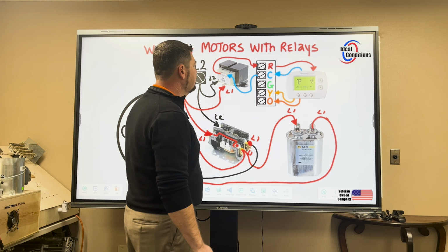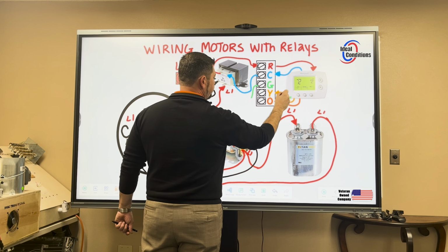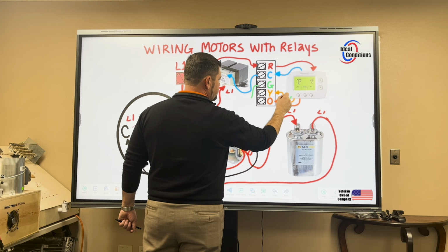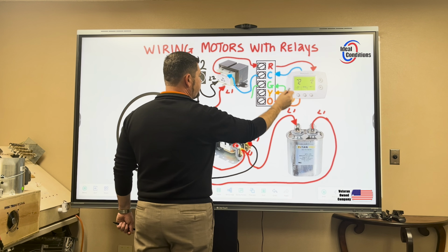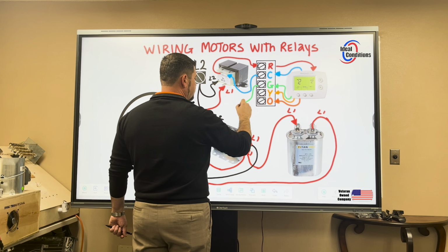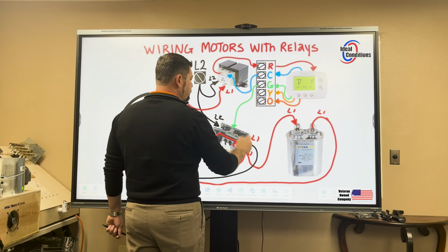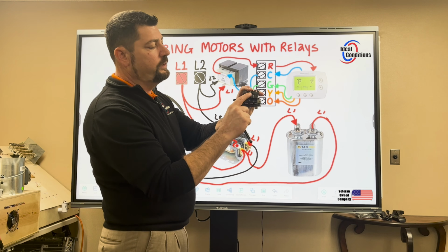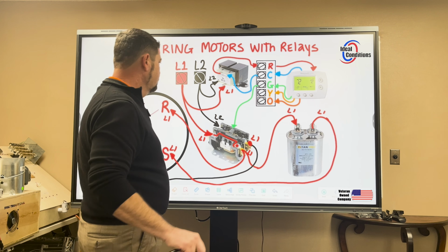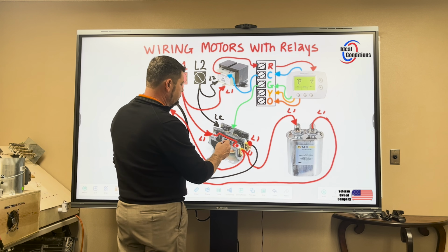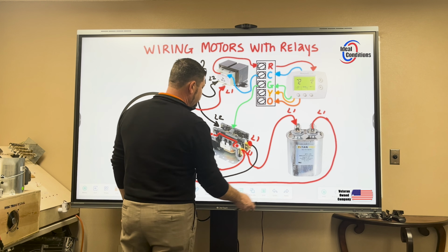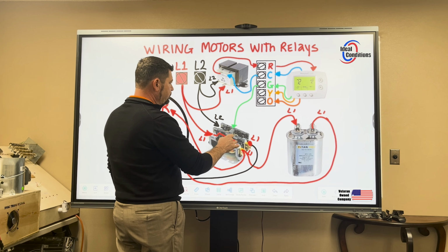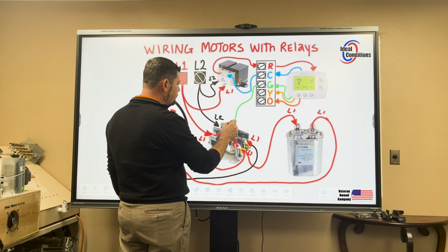And then using the G call, we're going to come out of the thermostat first, and let's provide G call from the thermostat to the terminal block. And then from here, we're going to come over and energize one portion of the coil of the relay, of the one pole contactor. And then in order for that to close, we're going to have to come back up and feed common back up here.